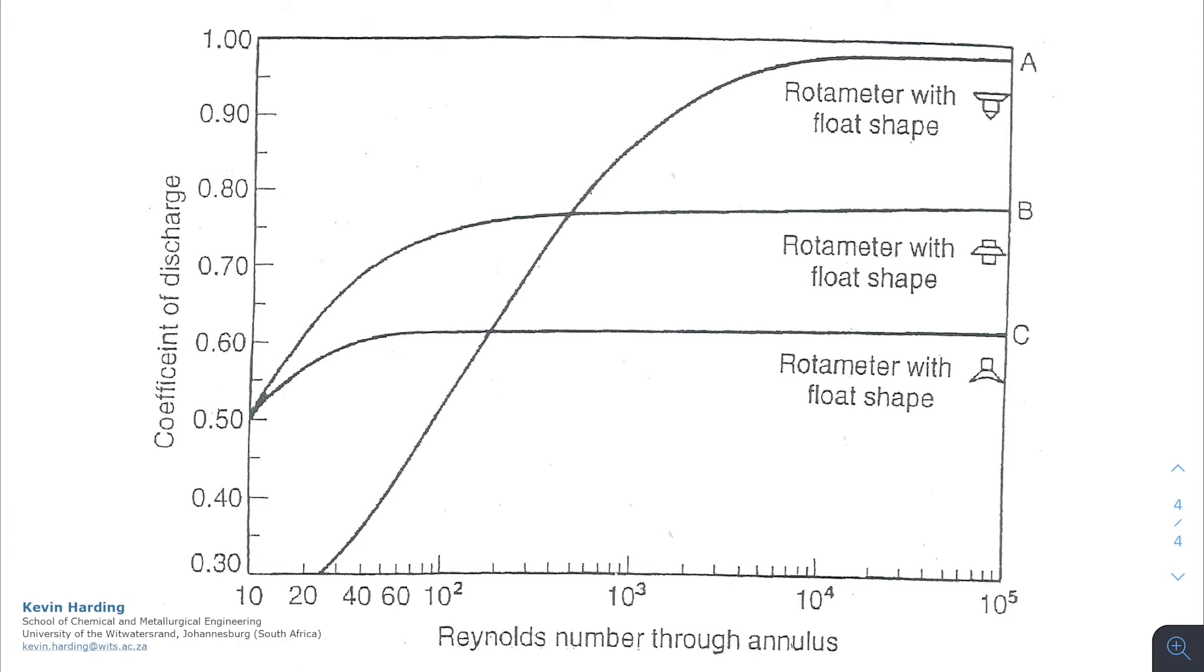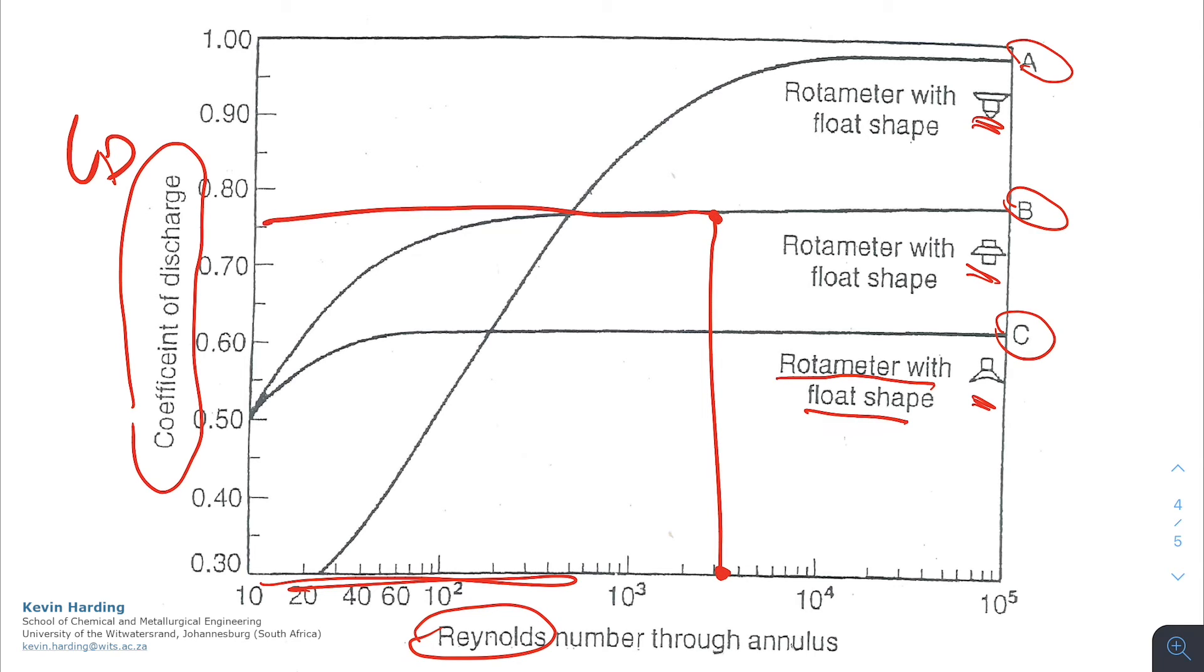This time, however, our Cd graph is a little bit simpler to use. We again have the Reynolds number on the x-axis to find the coefficient of discharge, which is our Cd value on the y-axis. However, this time we only need to look at three different scenarios where we have a rotameter with a float shape designated the letter A, B, or C, and there is a picture of each. Once you've got whether it's A, B, or C, we calculate the Reynolds number, read up to the curve, and then to the left to get our Cd.